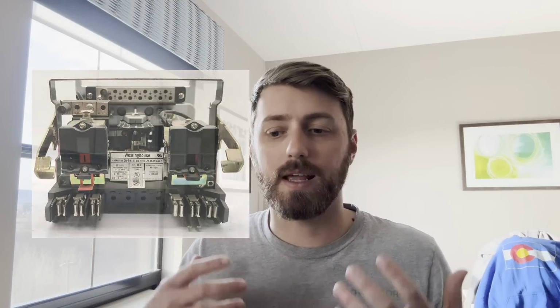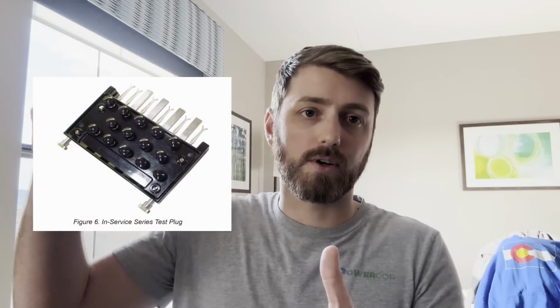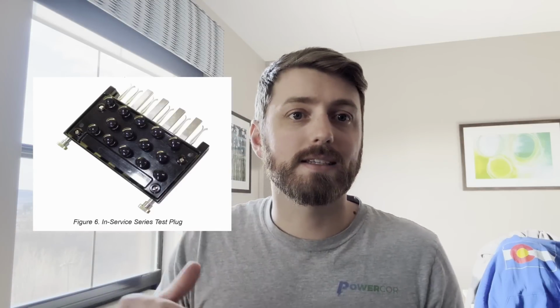But they also provided a convenient spot to connect a test switch paddle, which is a device where you could connect your relay test set or another current source, plug into the relay, and inject test current into the relay. It also allowed you to isolate just a trip circuit if you want to do something with it there, or isolate any number of other circuits.